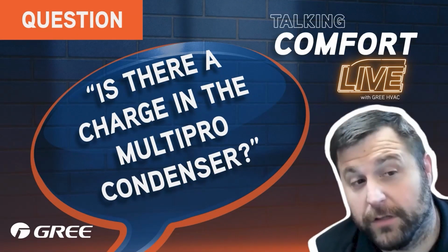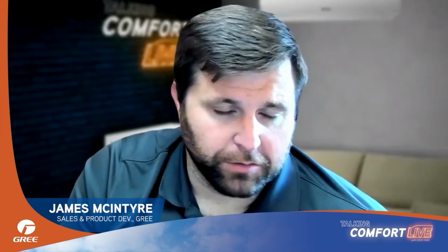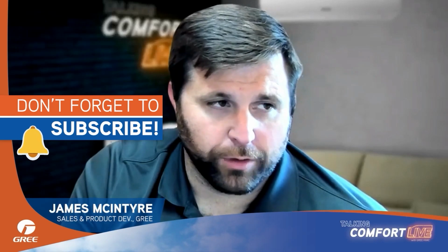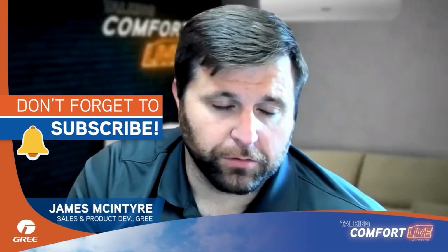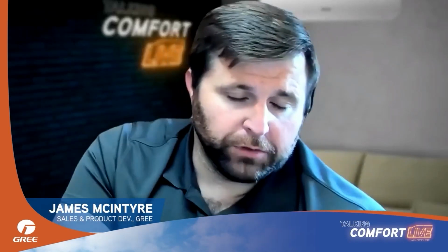So we had a follow-up question to the MultiPRO charging question on the 4 heads, if you recall. It said, is there a charge in the MultiPRO condenser? Yes, the MultiPRO condenser has refrigerant. But depending on the model, right? Some are not charged for any length of line set at all, and some of those models are charged for 65 feet. And I believe the delineation, correct me if I'm wrong, Greg, is that the standard heating MultiPRO is charged for 0 feet, while the Ultra Heat is charged for 65 feet. Is that correct? The Ultra Heat B revision.